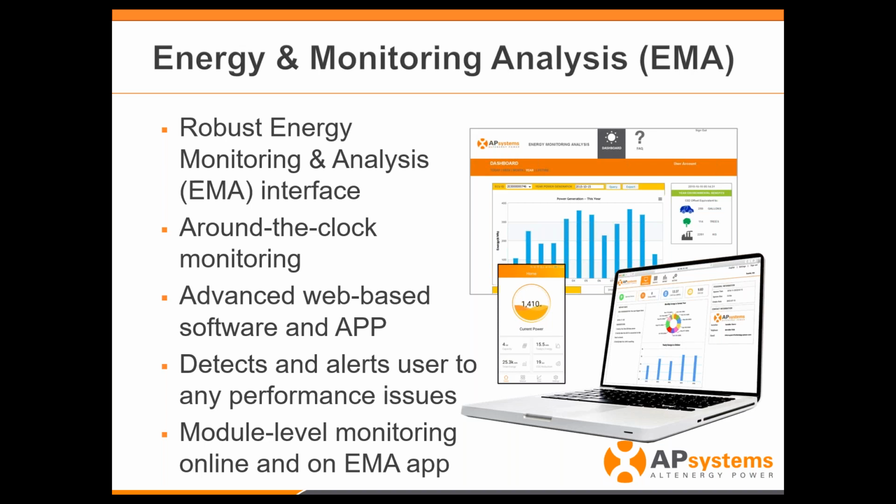Then at the 10-minute mark, what's your status? It will reply and come back and hold it. At the 15-minute mark, it will push out and say, what's your status? And at the 15-minute mark, it will take the 5, the 10, and the 15-minute data, pull it all together, and push it to the cloud. So we're going to have basically 12 poll cycles of that site per hour and 4 pushes of data to the cloud. When we're inside the EMA, I'm going to show you that information. It's nice because the granularity is there. You get the 4 pushes an hour, but it pushes those 5, 10, and 15-minute data.